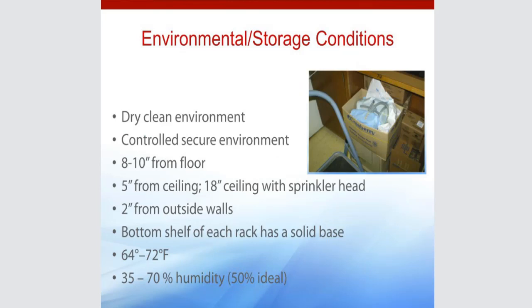So we talked about a dry, clean environment, a controlled environment. You want to make sure that your instruments are being stored 8 to 10 inches from the floor, at least 5 inches from the ceiling, at least 18 inches from the ceiling if you happen to have a sprinkler head there. It also has to be 2 inches away from the outside walls. And if you are using some type of a wire rack to store your instruments on, that very bottom shelf needs to have a solid base so that you don't get cross-contamination from housekeeping issues. We should be in a temperate environment, like most of our offices are kept, between 64 and 72 degrees. Humidity is a big deal with sterilization products. 50% is considered ideal, but you see the range that's listed there.